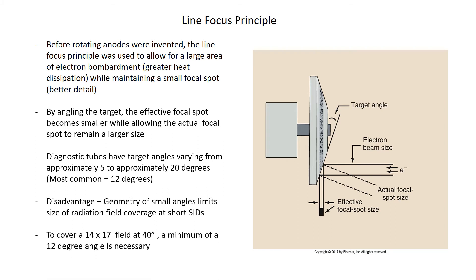In order to cover a 14 by 17 field at 40 inches, a minimum of a 12-degree angle is necessary. We utilize 14 by 17 fields for chest radiography, KUBs, and things like that, so we need that 12 degrees to cover the field with radiation.